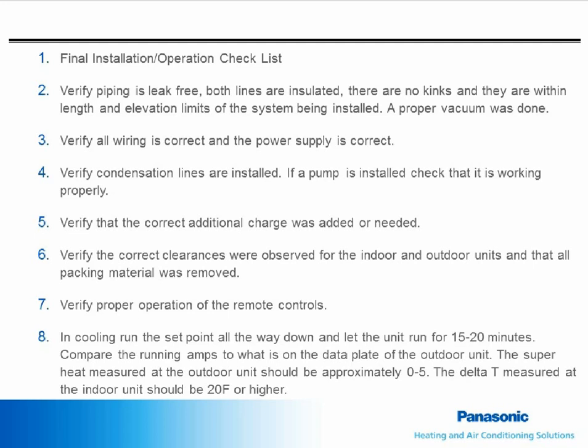Verify the condensation line is run and that it does not have a P-trap in it. If there is a condensate pump and the safety is used, make sure it's breaking the number 3 wire. Pour water into the drain pan to verify operation of the pump and proper drainage. If the unit needs additional refrigerant, verify that it was properly calculated and added. Make sure that all packing material is removed. Verify the remotes are working. The indoor units will beep when they receive a command from the remote. You can test this by pushing any button on the remote. If everything checks OK, the unit can be started.